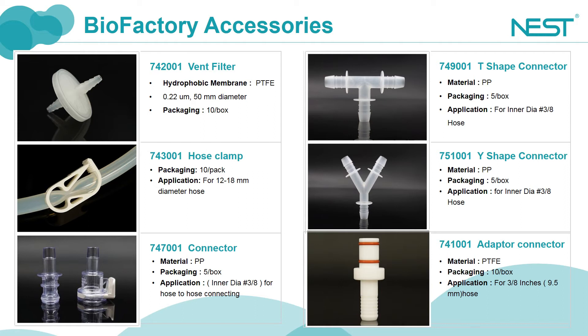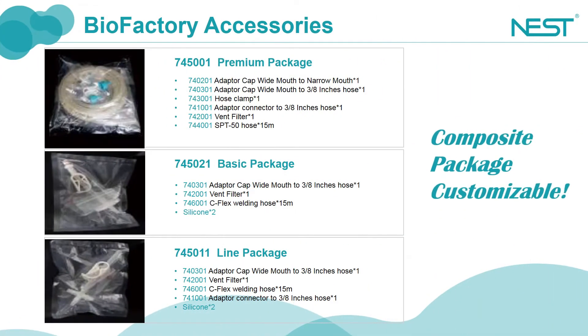Normally a filter, a clamp, and other fittings are attached on the tubing. We have designed three combined packages. The premium package is a combined package for tandem connection, while the basic and light packages are for venting. The difference between the basic and light packages is that there is no white adapter in the Line package, and the tube can be connected with the small opening transfer cover catalog number 740301 directly. The premium package includes a medium open transfer cover, a tube clamp, a small opening adapter, an air filter, and a 15-meter long silicone tube. The 15-meter long silicone tube can connect around 10 cell factories in series.